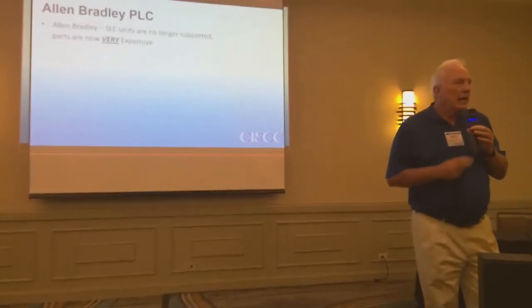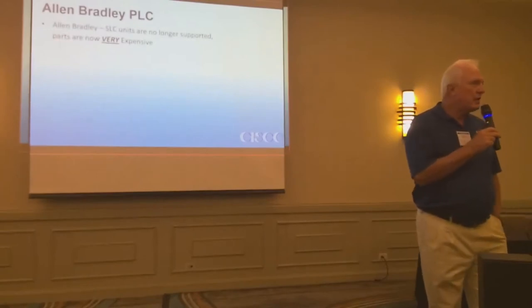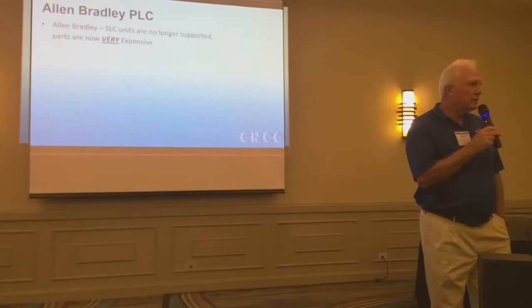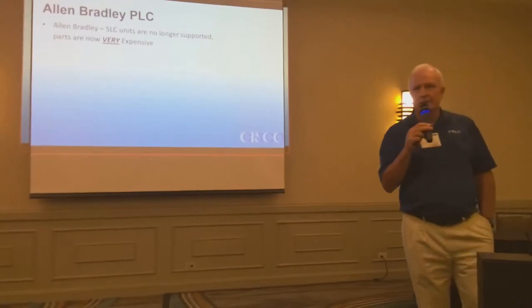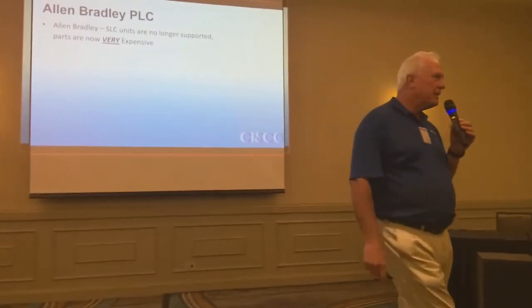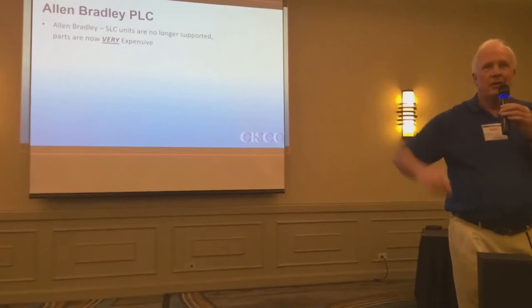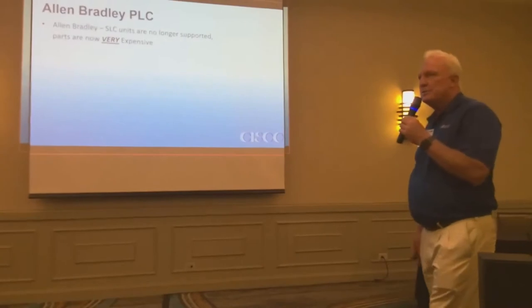On the Allen Bradley PLC side, the SLCs are no longer supported. And when I say that, could you still buy parts for an SLC PLC? Sure. If you want to buy an analog input module, it'll cost you about $8,500. They used to sell for about $450. You can buy an entire rack of CompactLogix for about that same price, and that's the CPU and Ethernet module and the whole thing. That's how they get rid of it. But they're running out of those parts too.